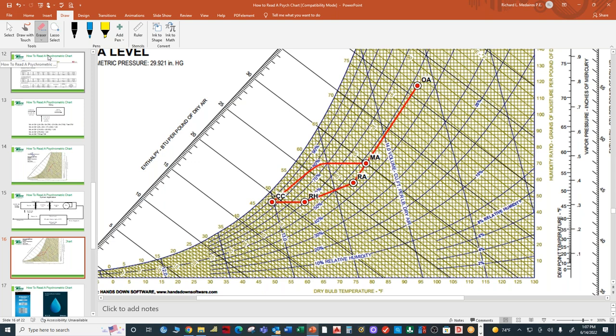And a lot of systems will use the refrigerant waste heat off of the air-cooled chiller. Or they'll interrupt the hot gas before it goes to the condenser and put in a hot gas reheat coil. So there's a variety of different ways to skin the cat without spending additional energy. Yep.